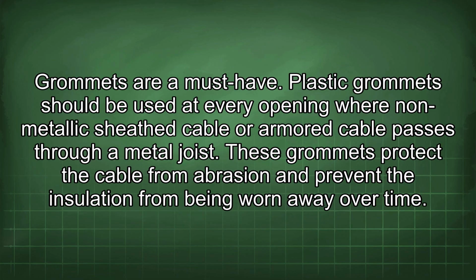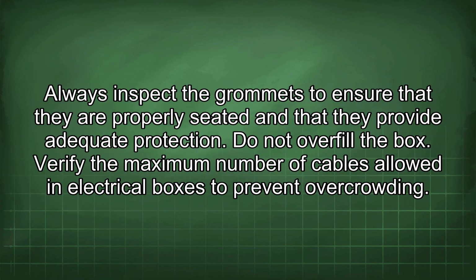Grommets are a must-have. Plastic grommets should be used at every opening where non-metallic sheath cable or armored cable passes through a metal joist. These grommets protect the cable from abrasion and prevent the insulation from being worn away over time. Always inspect the grommets to ensure that they are properly seated and that they provide adequate protection.